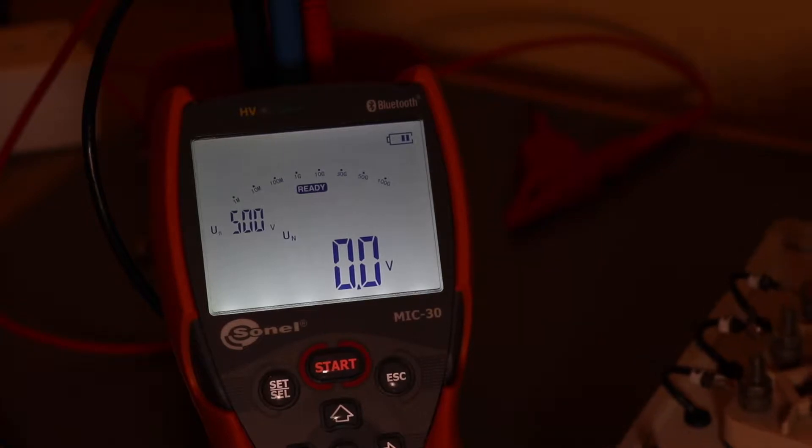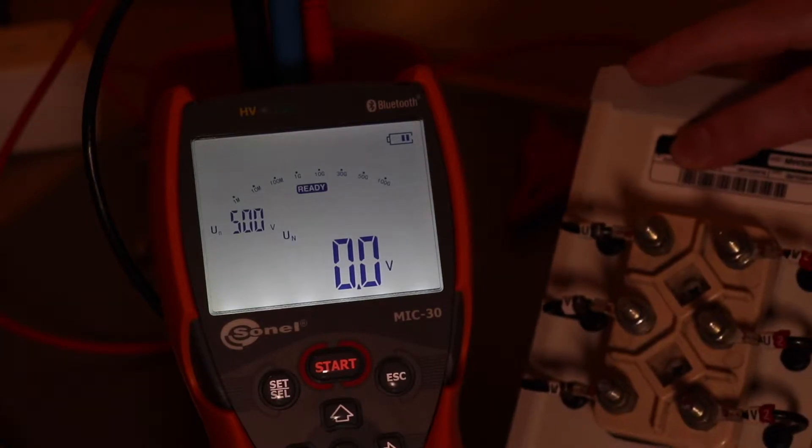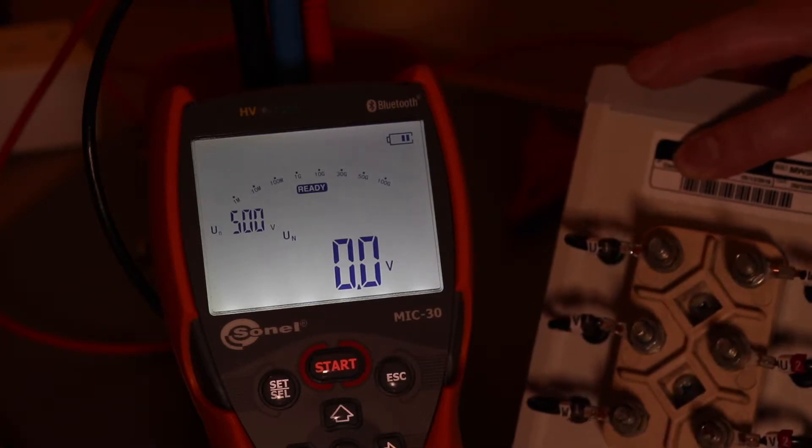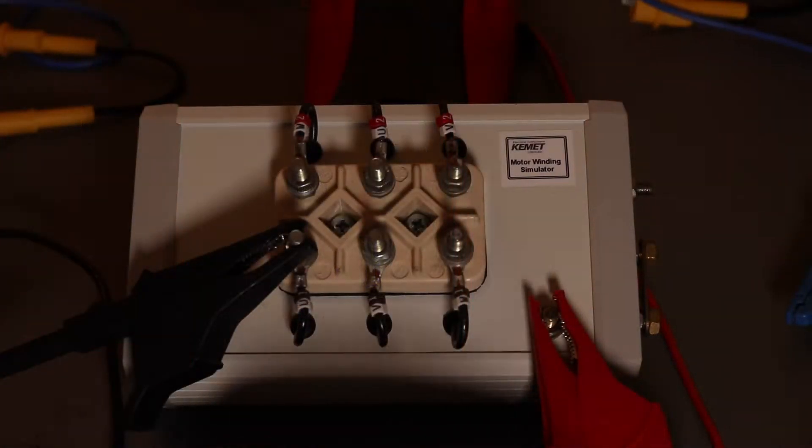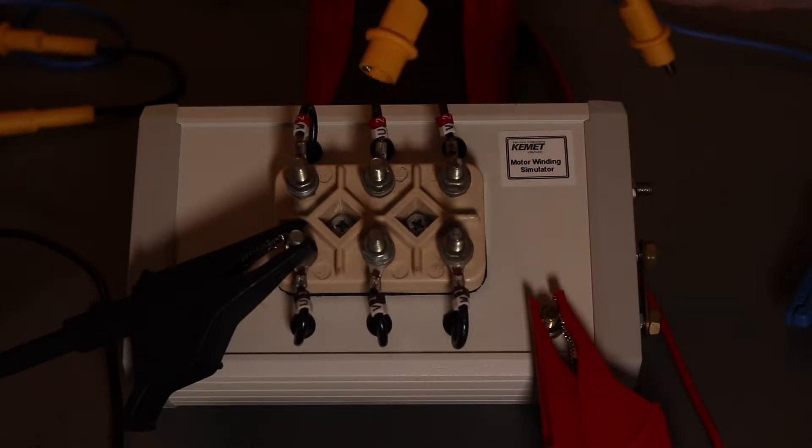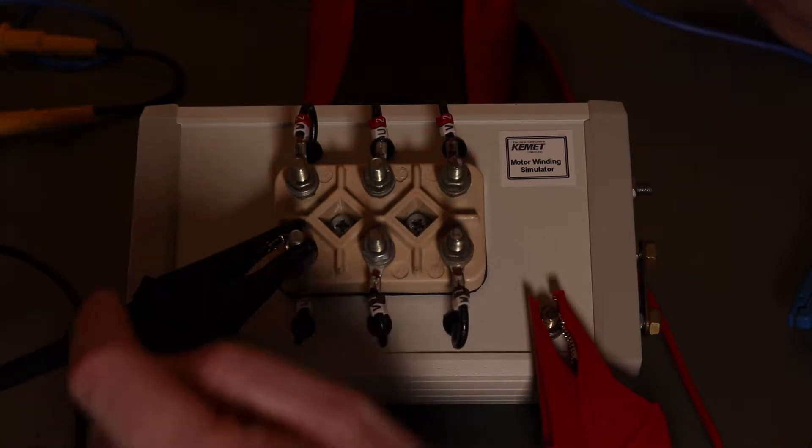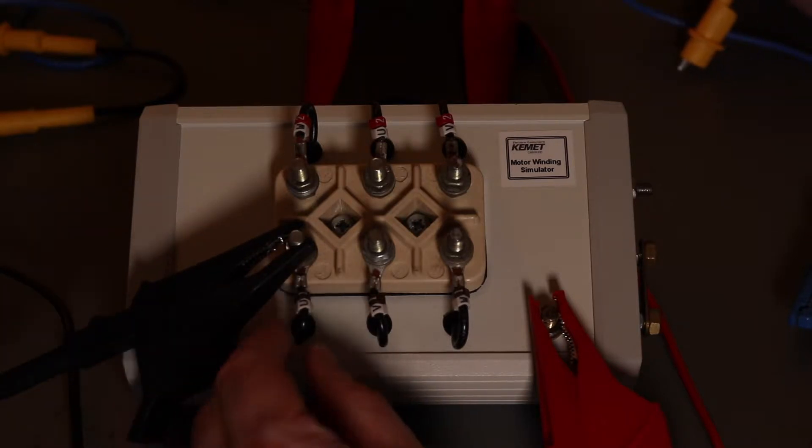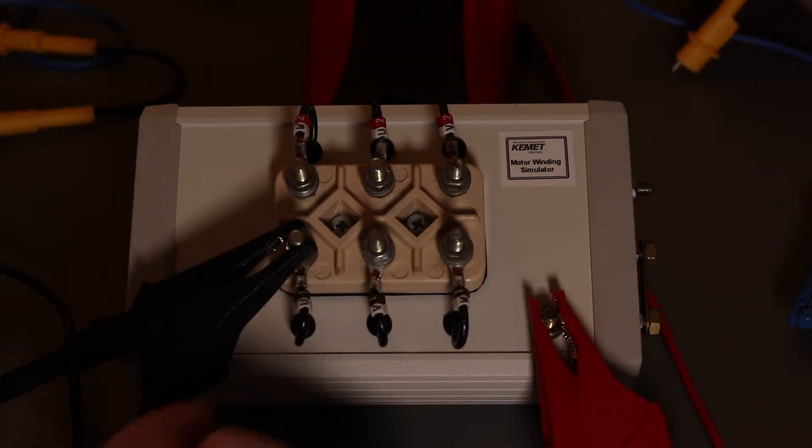In this video I'm going to demonstrate the use of the guard terminal on the Sonel MIC30 to take away leakage from the winding simulator. I'll demonstrate two different test configurations when using the guard terminal on an insulation tester. It's quite unusual for a 1000 volt insulation tester to have a guard terminal. Generally you would use it with a shielded test lead connected into the guard to remove any leakage between leads. But if you had a more expensive motor and you wanted just a true reading from the phase under test to earth, you could use the guard terminal to do that.